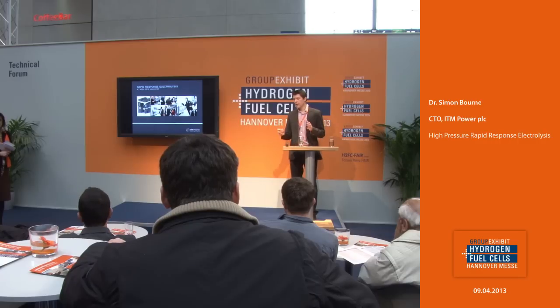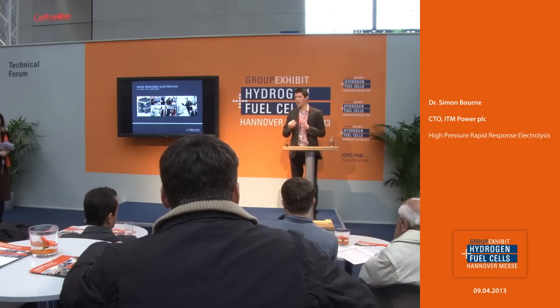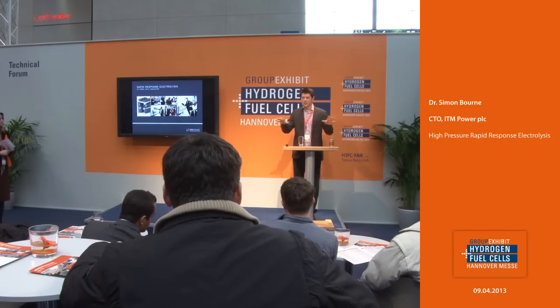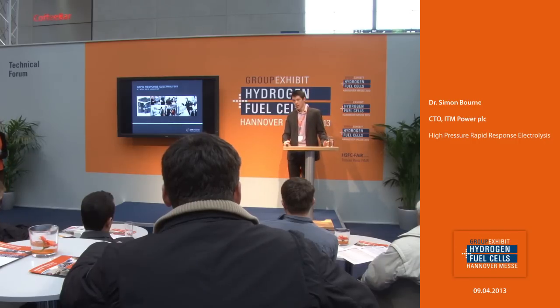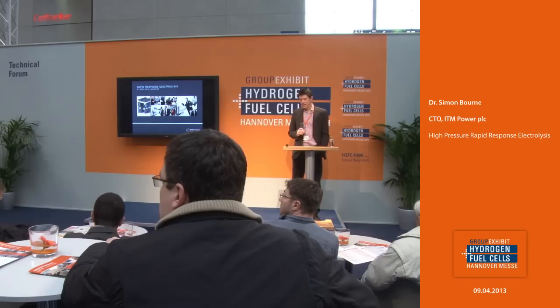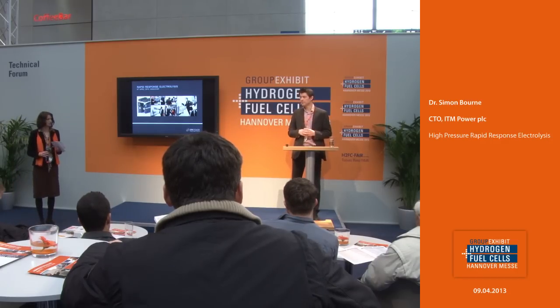Would you look to inject directly into the medium pressure gas grid? There are a few points with that. One attraction of injecting into the high pressure network is that there's a lot more natural gas moving through it, so you can put a lot more in before you hit the maximum threshold. However, those mains go in both directions so the hydrogen can find its way out into all different areas. If you introduce into the medium or lower networks, you always know which way the gas is flowing, so you know exactly what pipework and what applications that hydrogen is being delivered to. The early installations tend to be injecting into the medium pressure network, and also because you can use the output pressure from your electrolyzer directly — no need for compression. Exactly — compressors are a bit of a pain because they're expensive, inefficient and need a lot of maintenance. So if you can develop the pressure with the electrolyzer itself, it's energetically very efficient and eliminates one troublesome piece of plant.